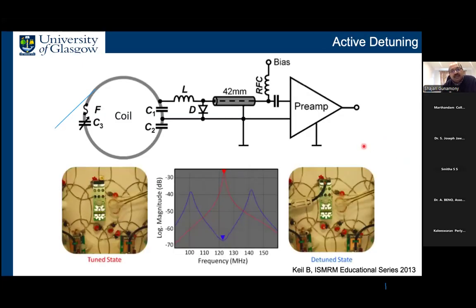I also mentioned a transmit coil and a receive coil, and they're all tuned to the same frequency. The receive coil is in the field of view of the transmit coil. If you are transmitting high RF power, when there is another coil in the field, it will induce a lot of current, and this can heat up the human tissue, which is a safety issue. So we have to switch off one coil when the other coil is operating. This process is called active detuning.